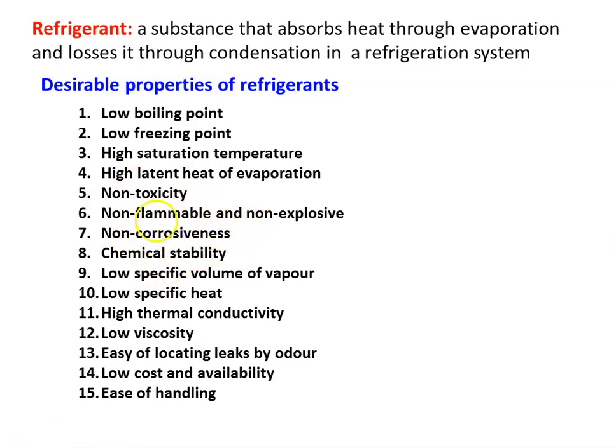Chemical stability means the refrigerant should not chemically react with other components. Low specific volume of vapor means the compressor size will be smaller. Low specific heat allows heat absorption; high thermal conductivity allows easy heat transmission; low viscosity allows easy flow. Easy location of leakage by odor means that if leakage occurs, the smell of the refrigerant should allow identification of the leakage. The refrigerant should also be cheap, easily available, and easy to handle.